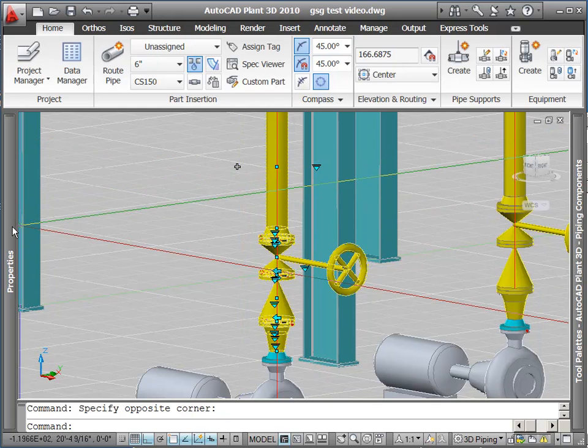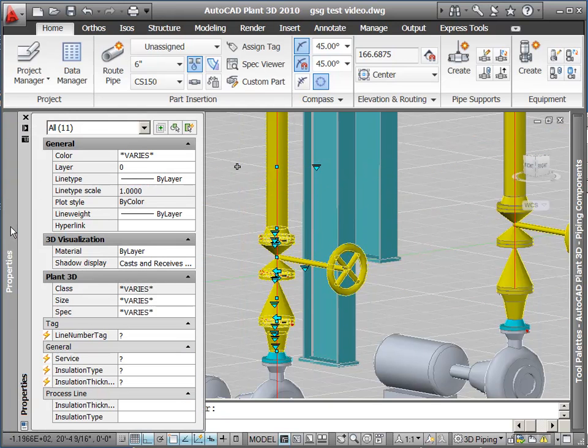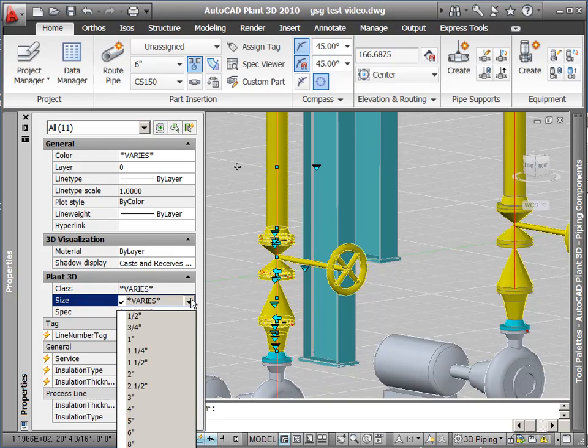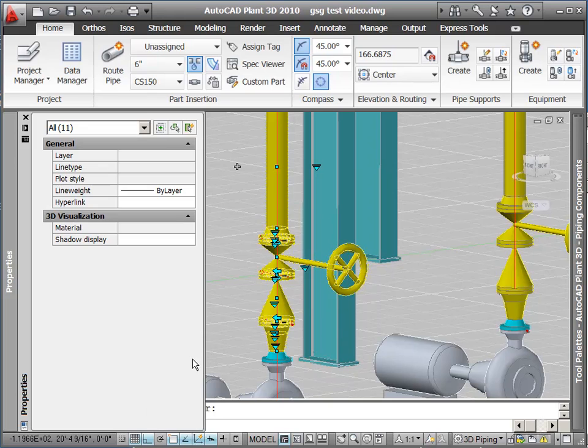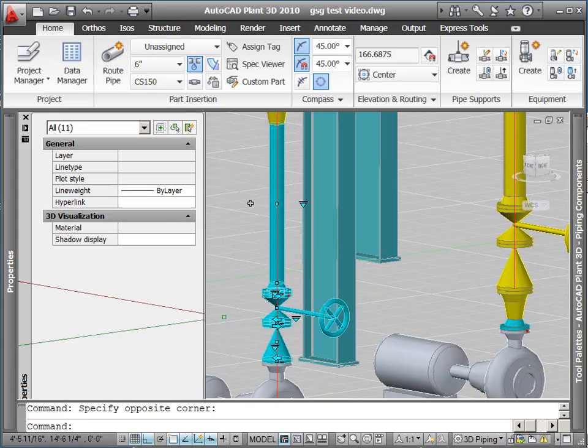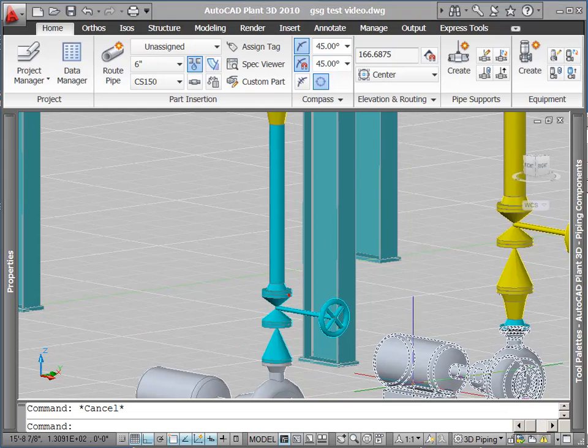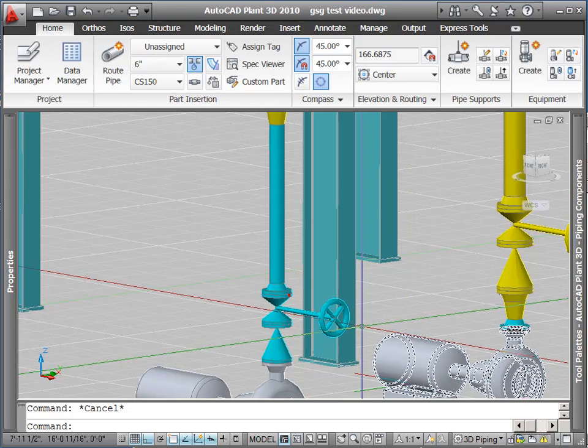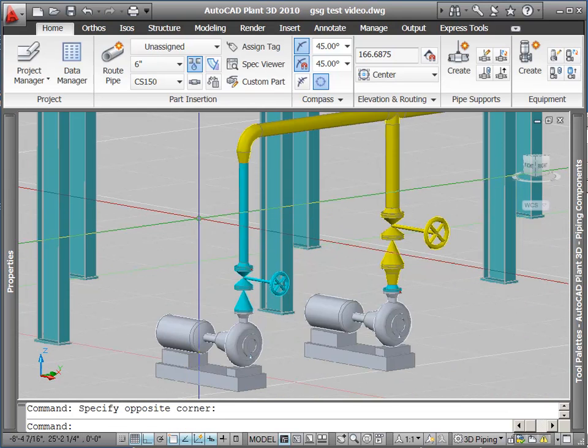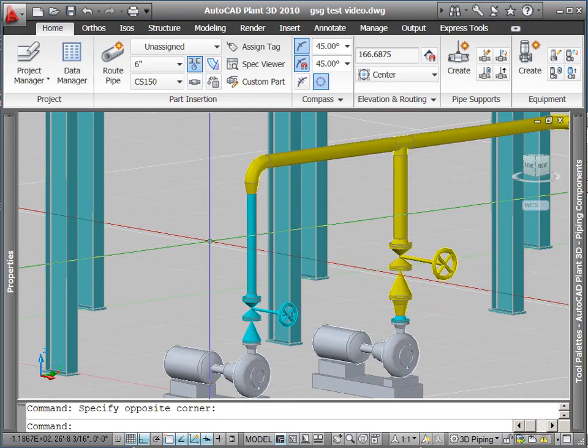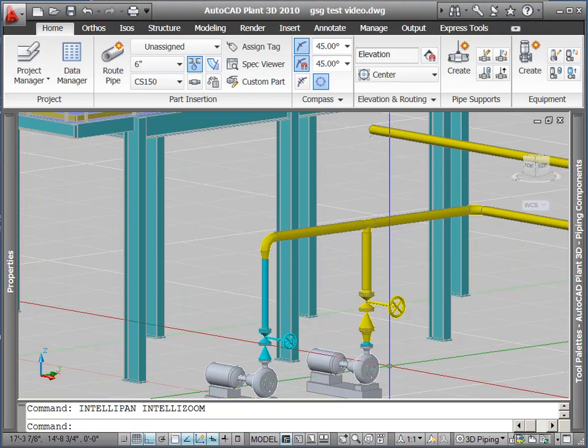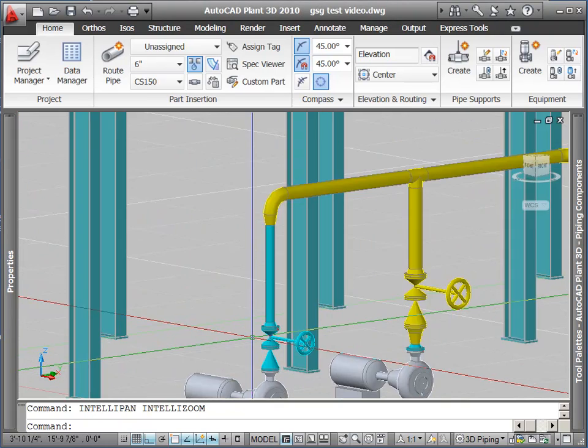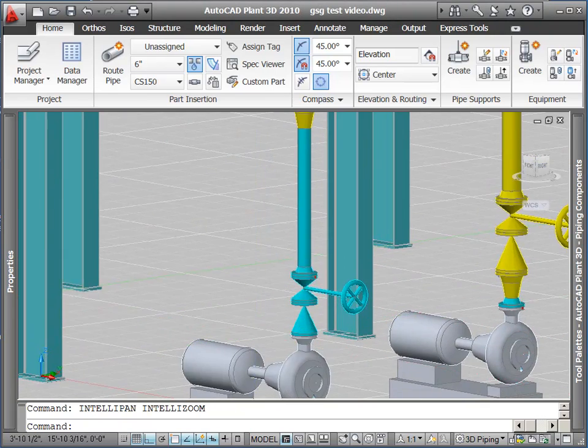Now I'm going to change size of this discharge line. I'm going to do that by selecting the items, and then in the Properties palette, change 6 inches to 4 inches, and just like that, it changes the size of my pipe and all my fittings, keeps everything connected just like they were before. It even removes the reducer and inserts the reducer as needed.